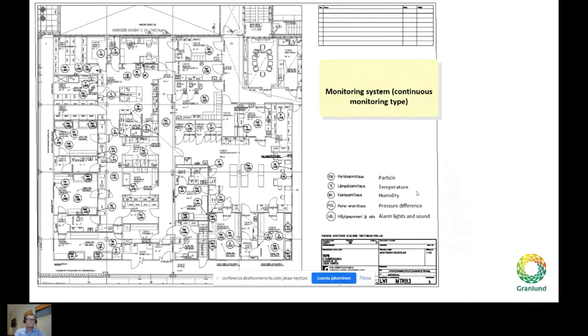The pressure control system consists of VAV dampers, so variable air volume dampers, room control panels and control centers. These VAV dampers regulate the airflow so that the room pressure remains at its set point. And this is quite a critical system in GMP facilities, because there are many different areas with these pressure differences, and we control and monitor that they are in use, and if not, then the process must stop. So if there is some kind of failure in this control system, it straight away makes it very difficult to work there anymore.